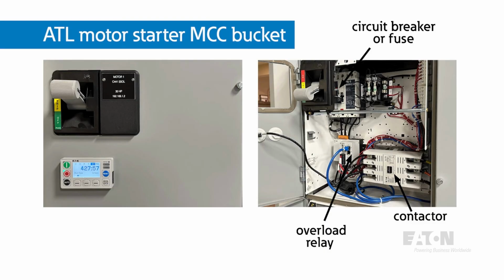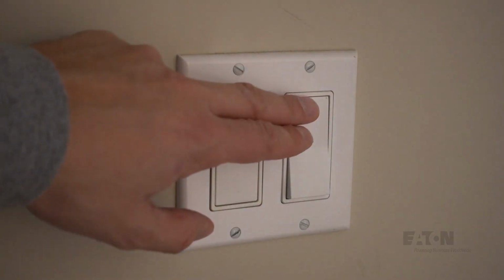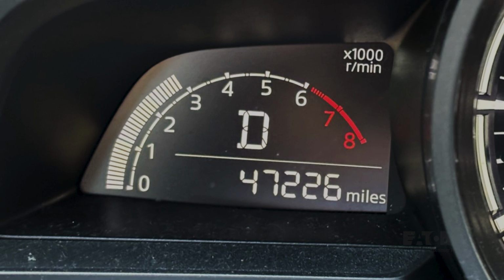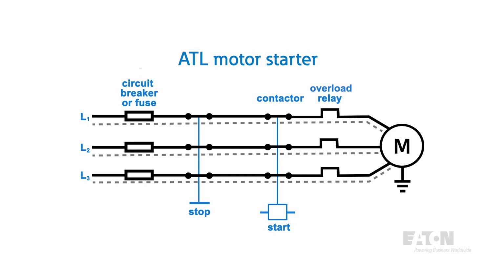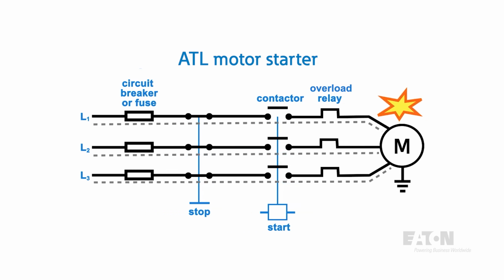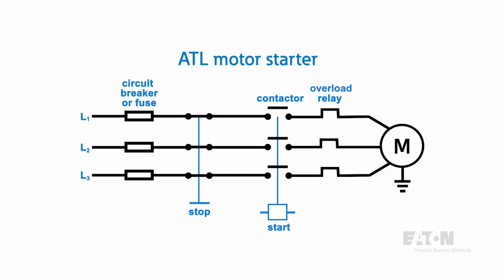An across-the-line motor starter simply connects the motor to the source voltage with a contactor, like a light switch turning on a light. If you were driving a car, an ATL starter would be like slamming the gas pedal to the floor. An ATL motor starter uses an overload system that will trip the contactor before the motor would be damaged if something significant happens to the load, like a locked rotor condition, or simply if you try to drive too much load with the motor.